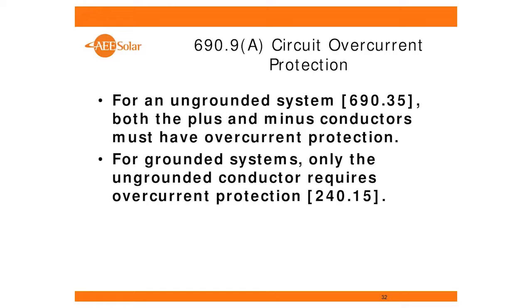So for ungrounded systems, the way it's currently written, we have overcurrent protection in plus and minus. In our smaller residential systems with non-isolated inverters, those are considered ungrounded inverters. The array is considered ungrounded. It's actually not true, but we'll go with it. We'll call it ungrounded.